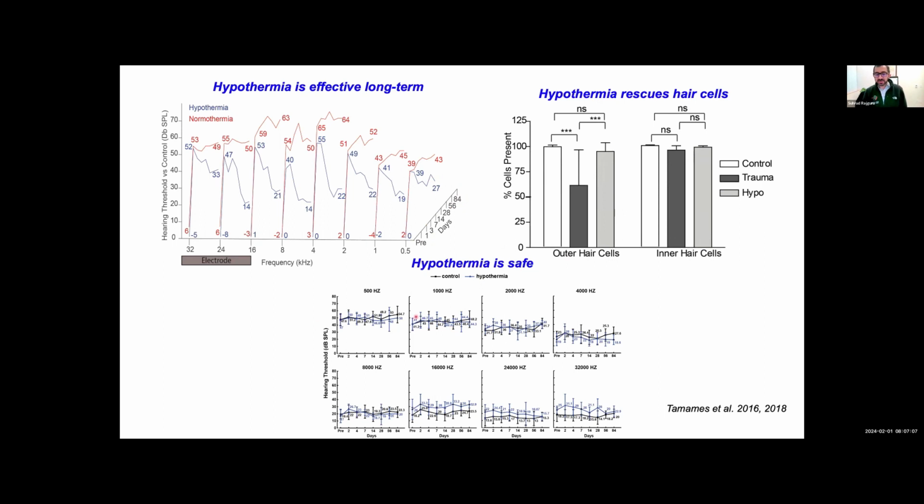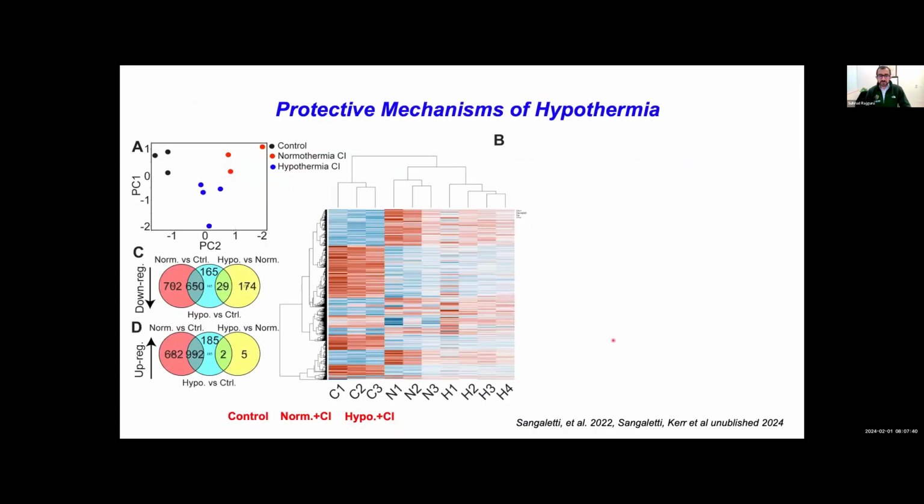So if you were to cool the cochlea compared to non-cooled cochlea without doing any kind of electrode insertion, would that affect any kind of hearing function, right? And at least at the mild hypothermia level, we didn't really see any damage within the cochlea or residual hearing issues. So these are the kind of data sets that essentially the FDA and the regulatory agencies, as well as a researcher, as a clinician, you want to look at and make sure that this is an application that's going to work before you move to a clinical application.